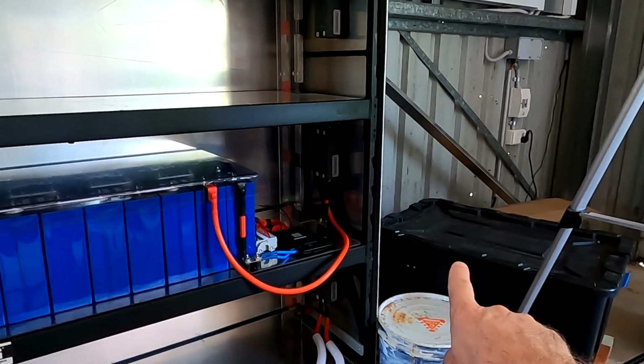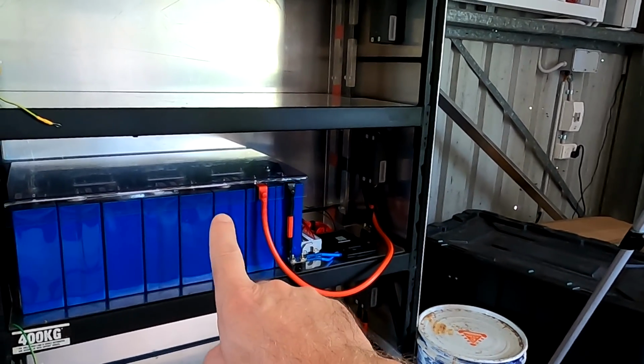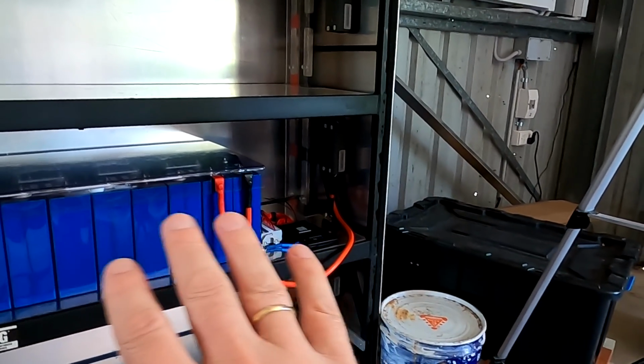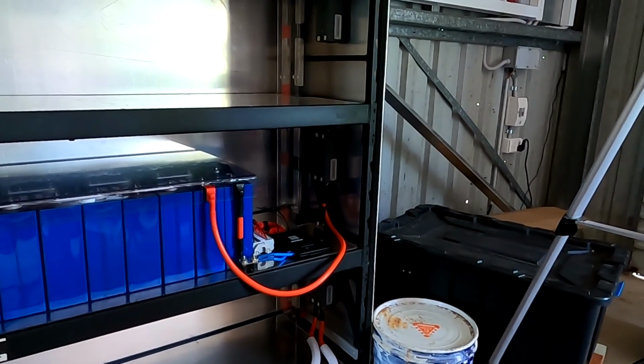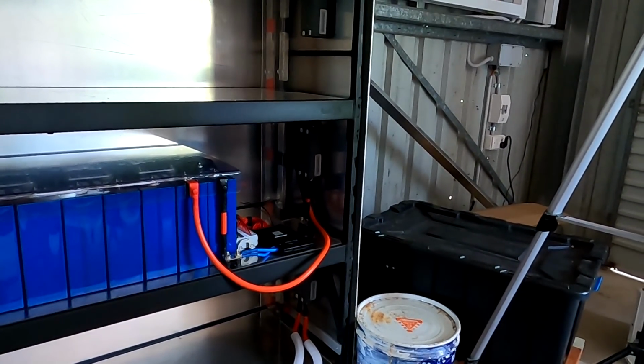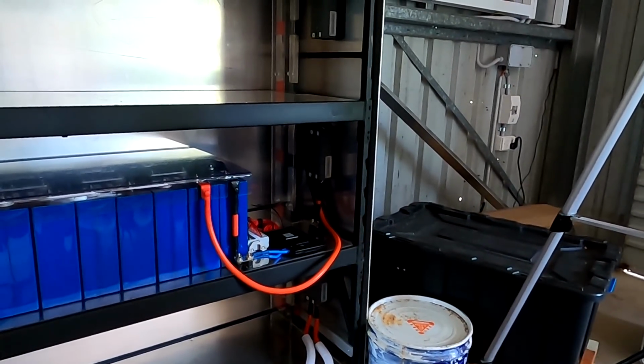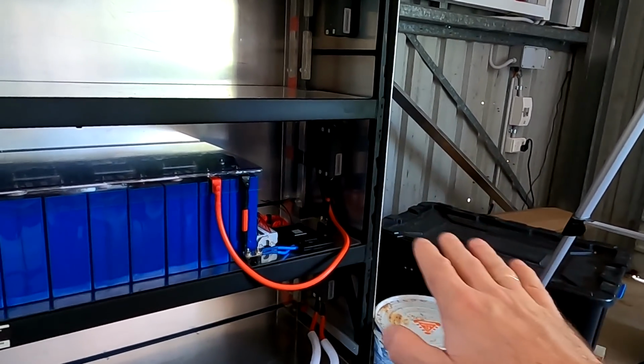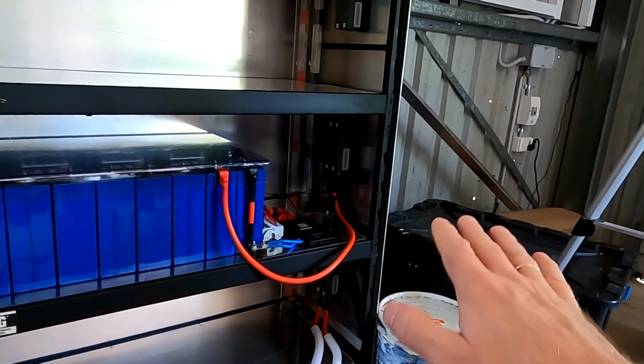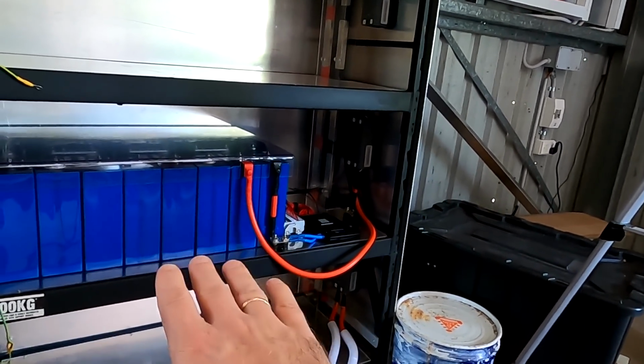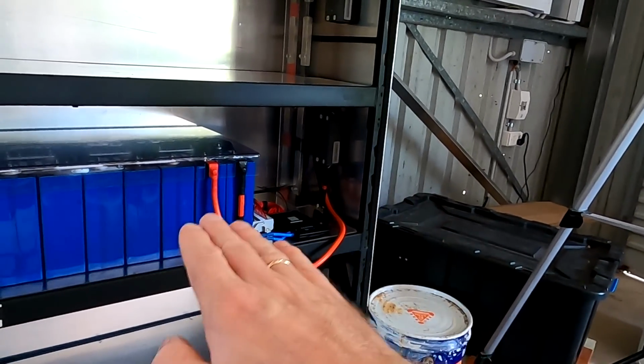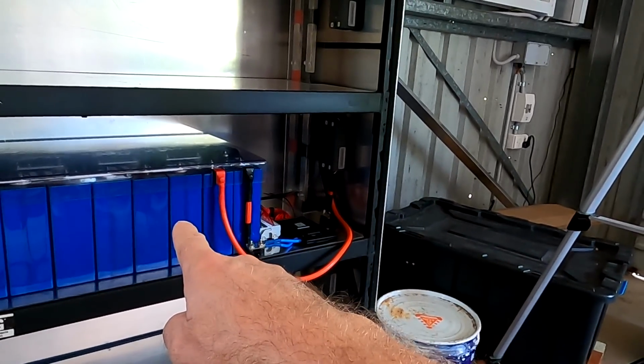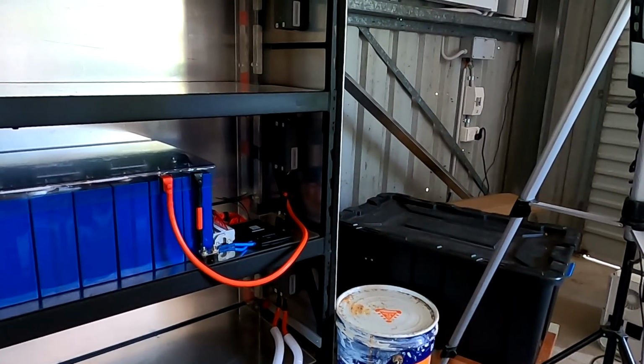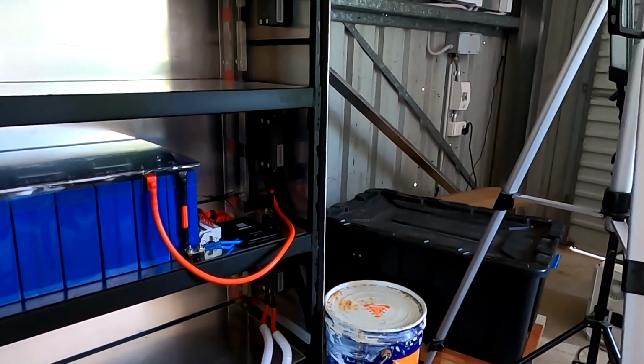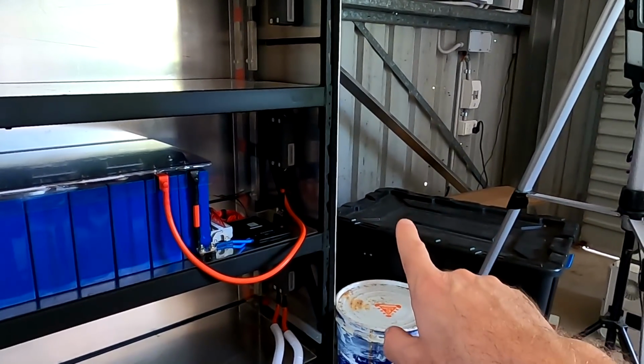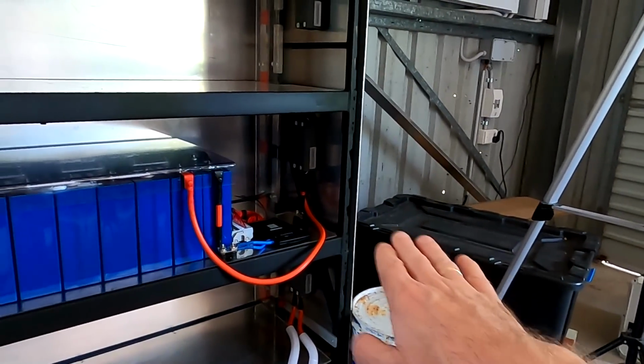Especially now we have the situation that the old battery is actually on a higher state of charge than the new battery. I'm not sure from this morning, because they both were on a fairly low state of charge, if there were any equalization currents flowing already, and they may have equalized now. So the voltages are identical. They are always the same because they are in parallel. There's no difference. Even if this one wants to go down from the voltage, it gets charged from the other battery. And this battery then keeps basically the other one alive.